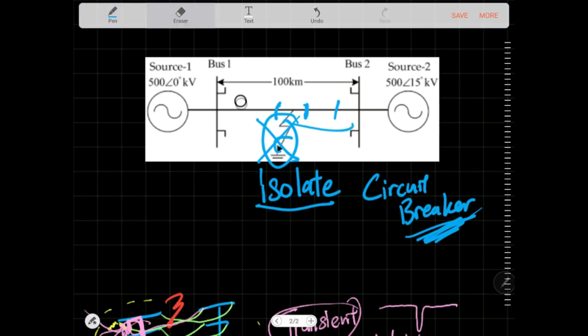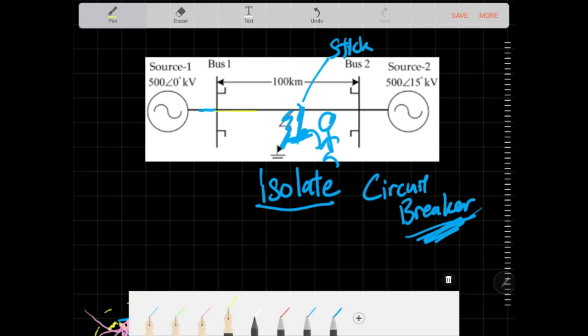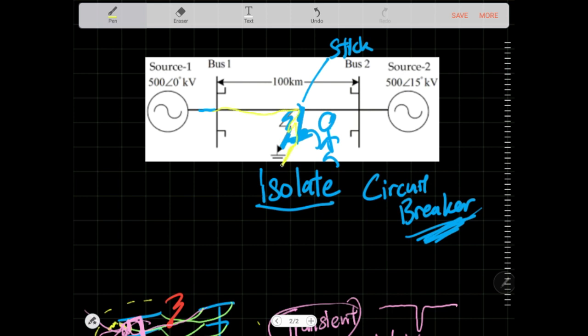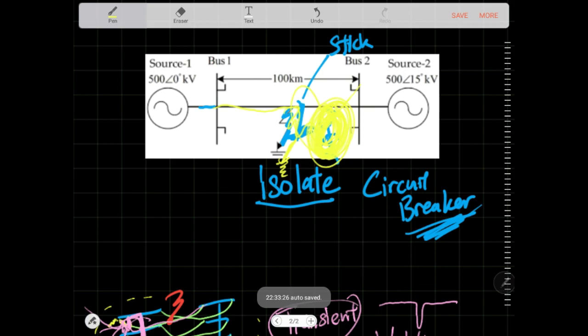But what if you do not isolate the line first? Say you just send your team to remove whatever is causing the fault — maybe a stick touching the ground. When a person grabs it, electric current will flow from everywhere, going to that person instead of to ground. The person gets electrocuted and most likely dies. That's why it's critical to isolate the line before any work is done.